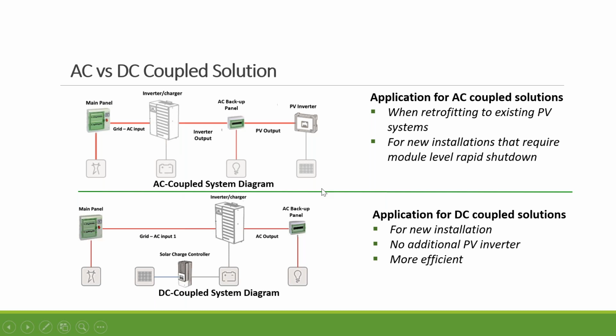Now, it's more popular for existing systems, an existing PV array, especially if you have microinverters or SolarEdge optimizers on the back of the solar arrays. Then you would do an AC coupled system. It's much simpler and easier. But the disadvantage is that you have two inverters here, so there are multiple conversions. You have DC to AC, now AC to DC, and if you want to discharge the battery again, you have to go DC to AC. So there's at least 5% more power loss.